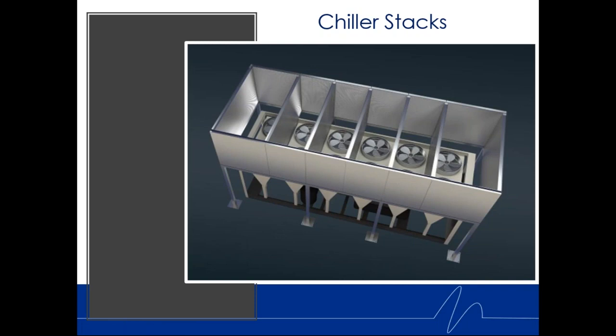This is an air-cooled chiller stack, another place we use noise block panels. These are all 4-inch thick, all perforated on the perimeter, perforated inner shell, solid outer shell. And then we put these divisional panels in here, perforated on both sides, basically working as absorption chambers, sound absorption chambers.